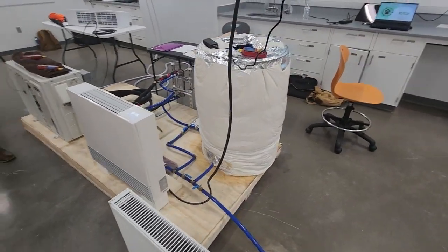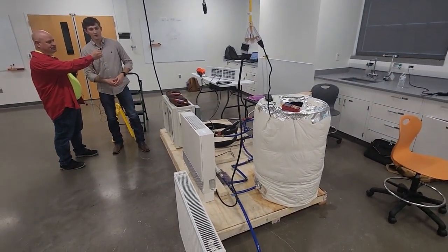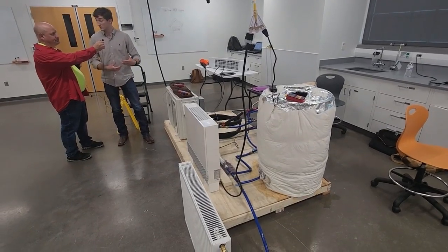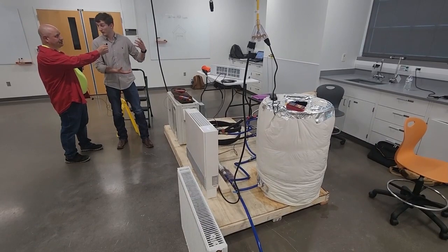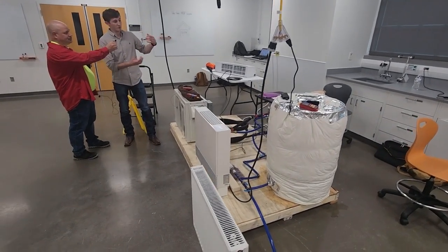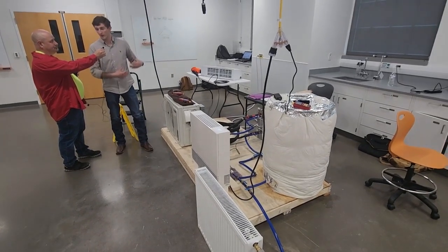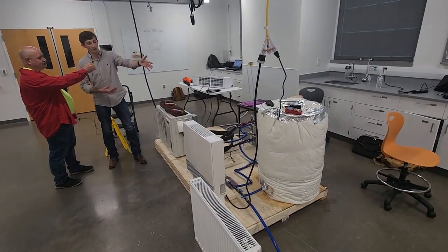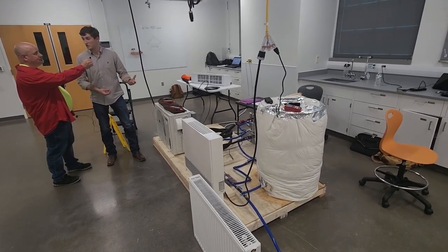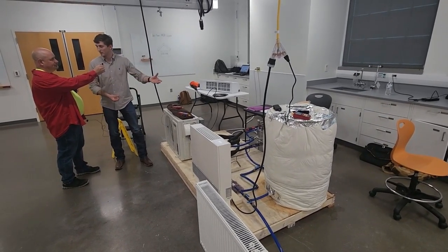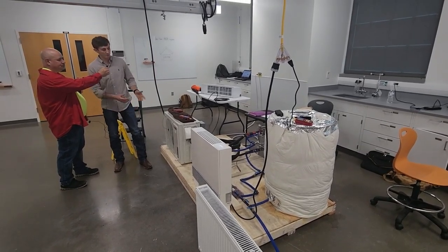So what's really unique about this design is the thermal energy storage tank. The concept here is when you have excess energy in the daytime, since it's a zero energy home, you have excess energy when you have solar panels that are getting sun. You'd use that excess energy to heat up your tank. So then when you don't have any sunshine, you can use the hot water to pump through your system and you can still get heating for really cheap, right? It barely takes any power to pump things. What takes a lot of power is heating stuff up. So that's what we're looking at here.